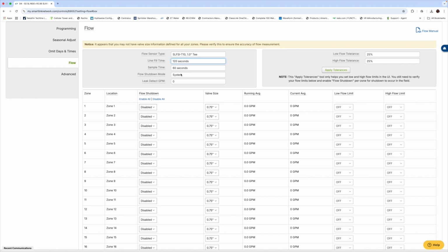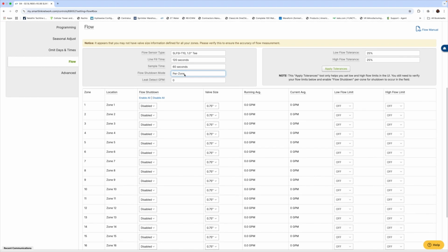Now, flow shutdown mode, we have two types. We have system, which simply means if there are two back-to-back errors of the same nature, high flow or low flow, that we will enable the master valve shutdown and terminate the program. And then we have per zone. What that allows us to do is just to continue to run every zone within the system. So if we have a stuck valve or a broken main line, we'll essentially run through all of the zones to see if we ever operate within the parameters set. And if not, you'll receive a flow alarm for every single zone that ran within the program. So those are the two options, and we leave that to your discretion.